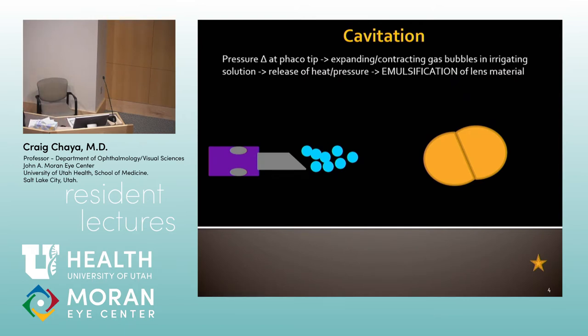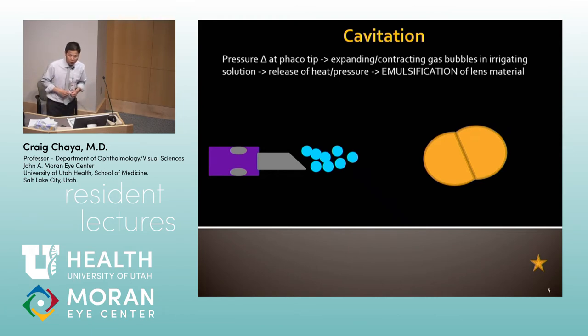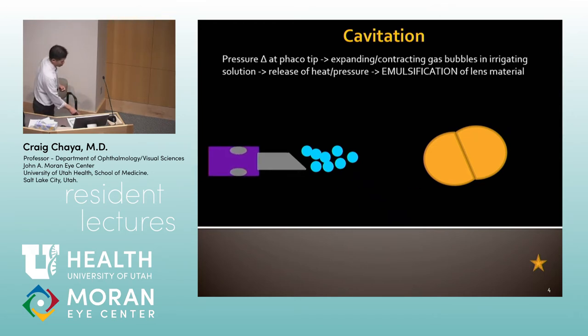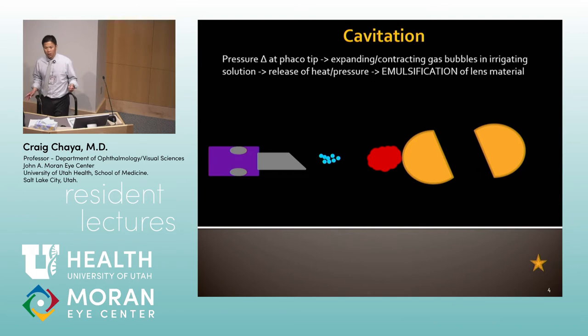Actually, cavitation is helpful — you do need some cavitation for phacoemulsification to occur. There's a pressure change that occurs at the tip. When that pressure change occurs you get gas bubbles that expand and contract, and it's the collapse of those gas bubbles that releases energy — heat and pressure — that allows you to emulsify the piece. So it's actually a good thing. Phaco tip vibrates, bubbles expand, bubbles collapse, pieces break up. That's cavitation.